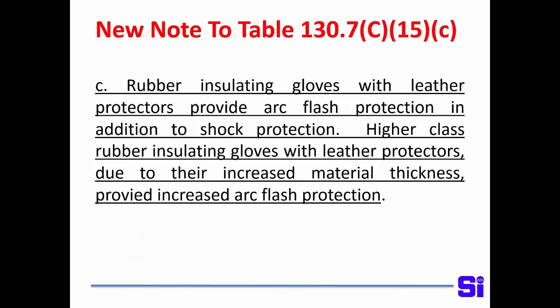And at one of the ASTM F-18 committee meetings I attended, one of the utility people stood up and said, I've never seen somebody with hand injuries that was wearing rubber insulating gloves and leather protectors. The gloves may be damaged, but the person's hands were fine.